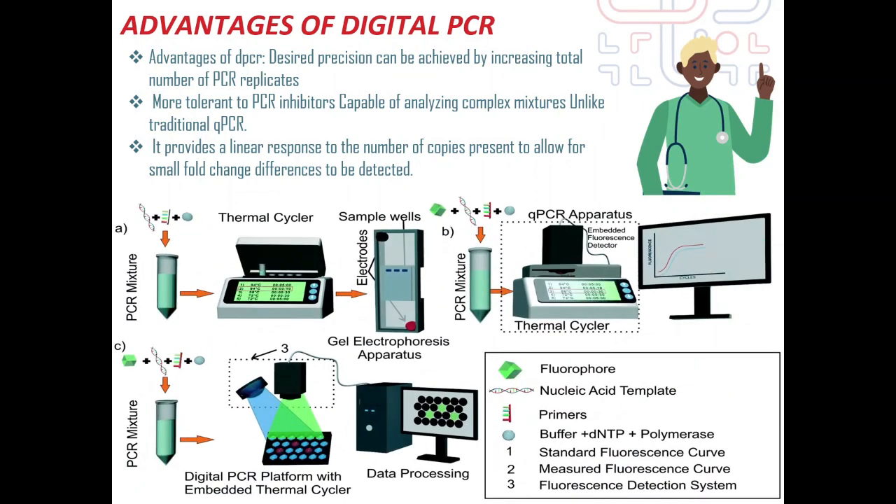In this picture we can see the working of a nanoplate-based digital PCR. Firstly, we prepare and load our digital PCR instrument — measure DNA amount and purity, set up our digital PCR system, prepare our reaction mix in a pre-plate, then load the plate and start our digital PCR machine. Second, we run and amplify: the plate is processed in the priming/rolling module, where the reaction mix of each well is partitioned into a thousand individual reactions, and PCR is performed on a thermocycler. Thirdly, we analyze the dPCR result by selecting the application to view a heat map, histogram, etc.